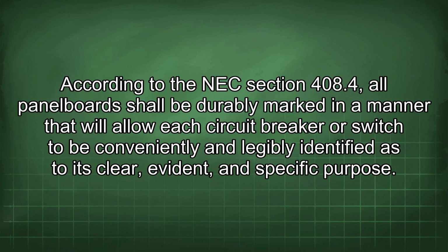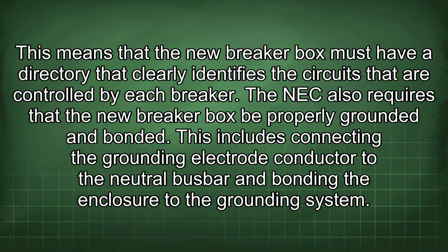According to the NEC Section 408.4, all panelboards shall be durably marked in a manner that will allow each circuit breaker or switch to be conveniently and legibly identified as to its clear, evident, and specific purpose. This means that the new breaker box must have a directory that clearly identifies the circuits that are controlled by each breaker. The NEC also requires that the new breaker box be properly grounded and bonded.